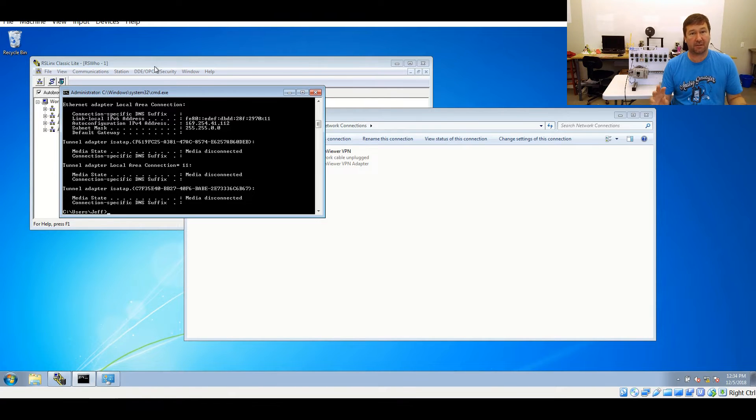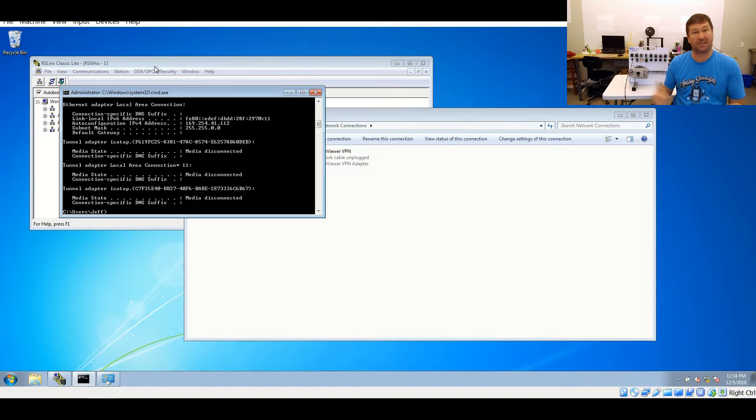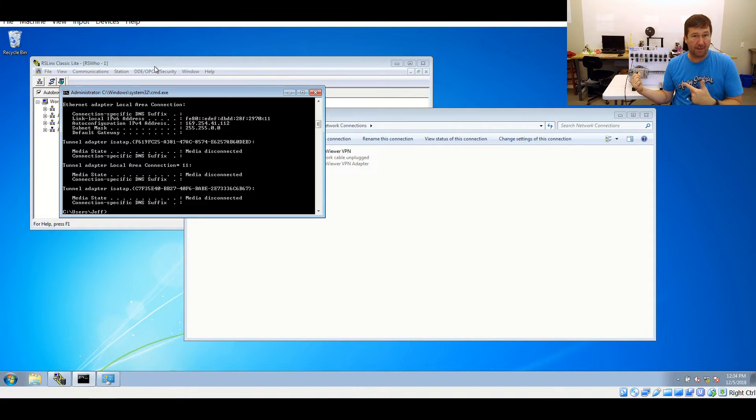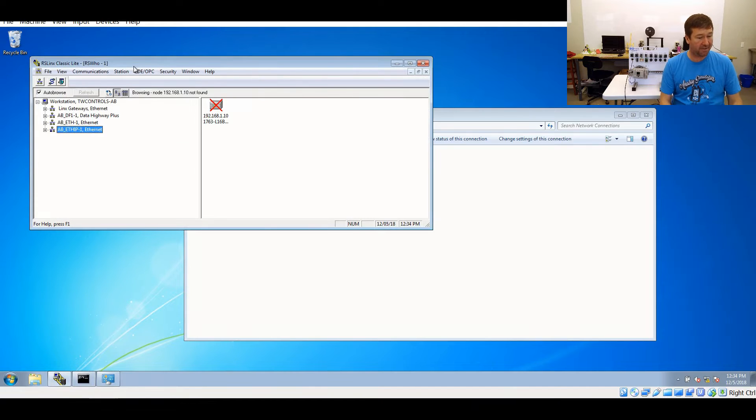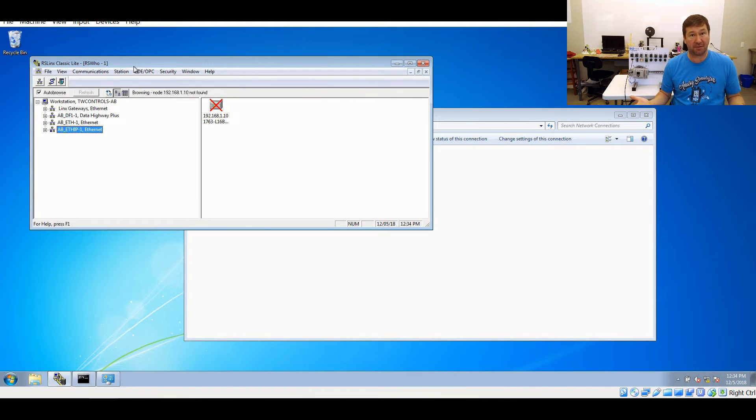We can see, I said earlier the first three octets need to match and 169.254.41 does not match 192.168.1. So if we go back to RSLinx Classic, we can see we have a red X through it.